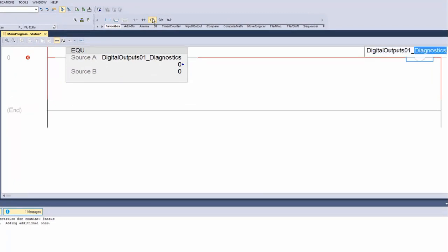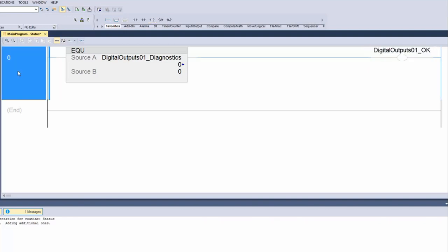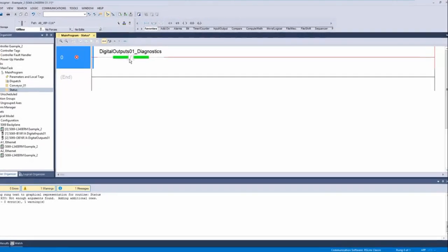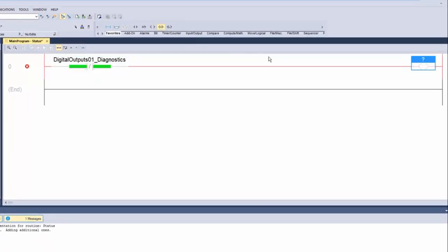When we have a supervisory level program, we can connect the hardware not faulted output parameter to the relevant parameter in the supervisory level program module. We do this for each hardware module in the project. Because we chose the InOut usage that updates synchronous to the hardware's RPI, the fault data will always be as up to date as possible.